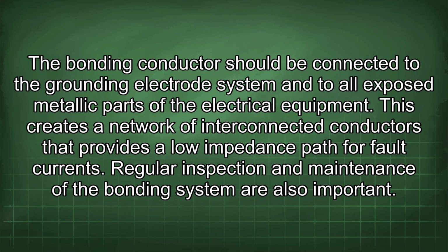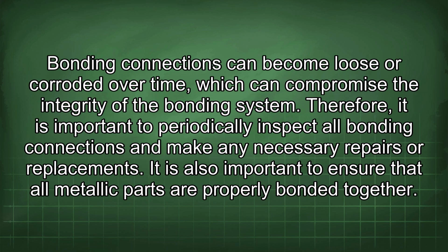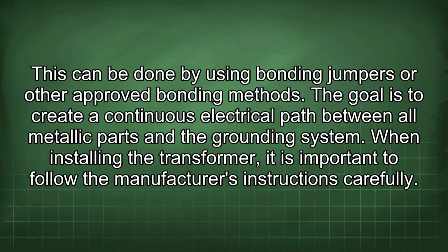Regular inspection and maintenance of the bonding system are also important. Bonding connections can become loose or corroded over time, which can compromise the integrity of the bonding system. Therefore, it is important to periodically inspect all bonding connections and make any necessary repairs or replacements. It is also important to ensure that all metallic parts are properly bonded together. This can be done by using bonding jumpers or other approved bonding methods. The goal is to create a continuous electrical path between all metallic parts and the grounding system.